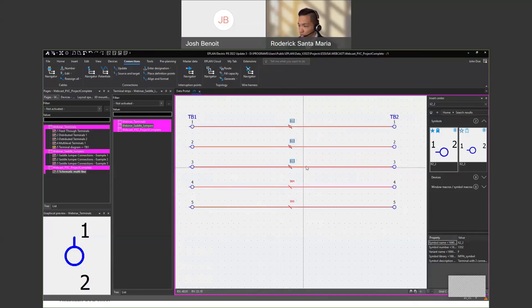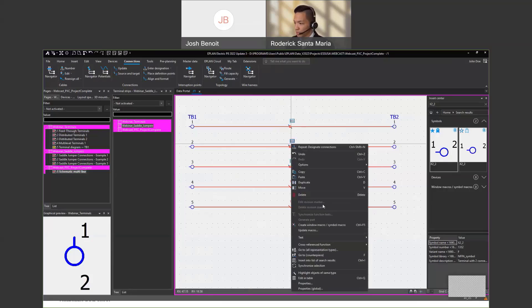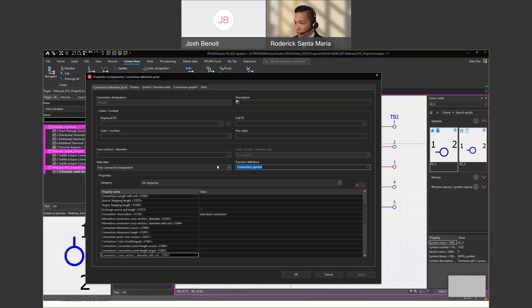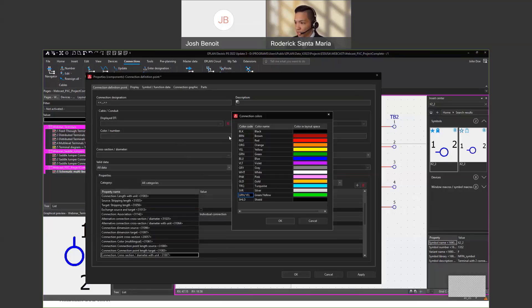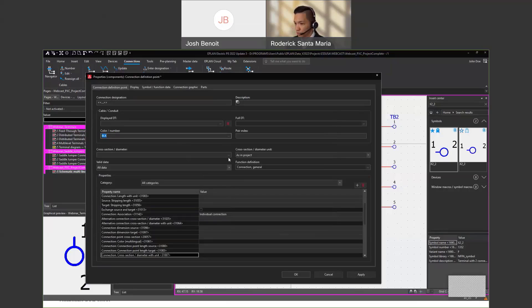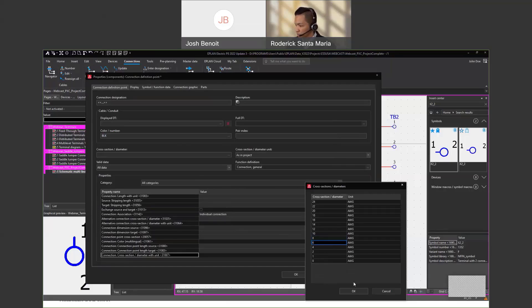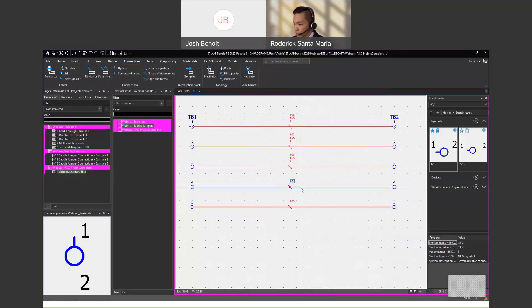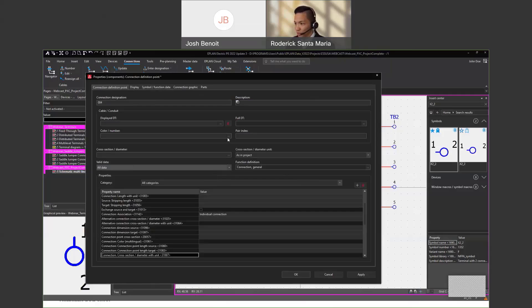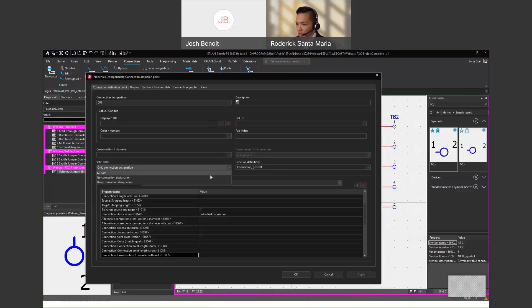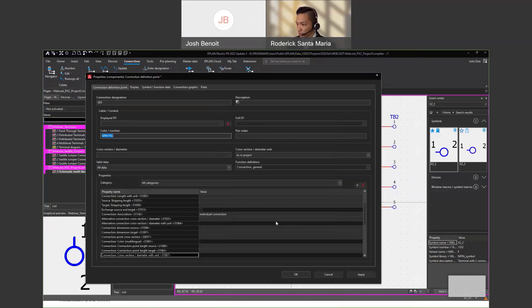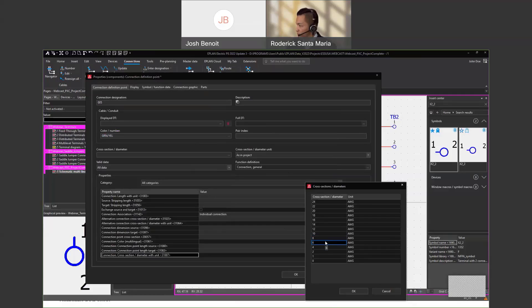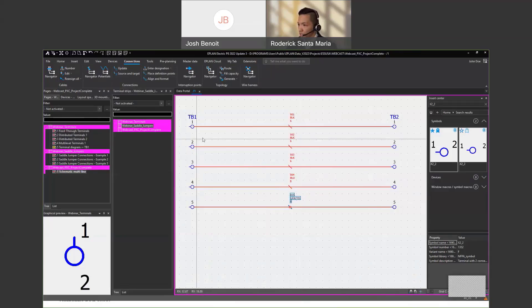From here I can set the wire colors for my three-phase incoming power. I can go to Properties and change the data to choose the right color — I'll make this black and then choose a diameter of 6 AWG. I'll also change the color number and cross section for my neutral — this will be blue, and I'll change this to 8 AWG. Same for my ground — I'll change this to green-yellow, which is a typical color for a ground, and also make this 6 AWG.